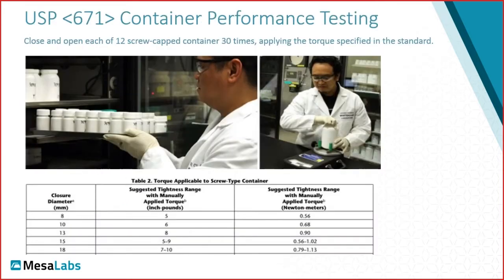One good example of that, as it comes to torque testing, is USP 671, which is required for container performance testing. This method requires that the operator closes and opens a screw cap, 12 of them, 30 times. And if we are talking about a package design company, a cap manufacturer, or even pharmaceutical companies, when they do this type of test, they are not doing it just for one product. They might be doing it for hundreds of batches, and over time that could really be demanding.